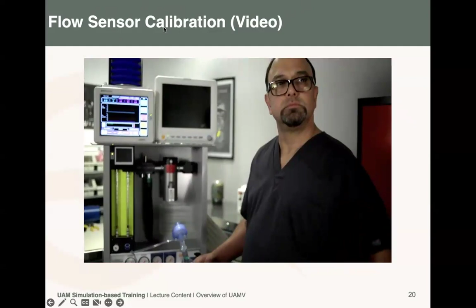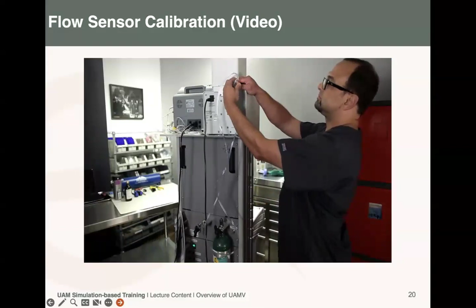Disconnect the ventilator drive hose from the ventilator and attach the red plastic adapter to the 17mm bellows driver taper on the rear of the ventilator bellows assembly. Connect the patient flow sensor with the flow in the patient direction. Blue line closest to the patient, clear line closest to the ventilator. To first calibrate in the forward direction, press the Flow Cal button. Press Calibrate Patient Flow. Press Yes to start calibration of the inspired flow. When prompted, turn the flow sensor around to calibrate the expired flow and press the Continue button. Note: the ventilator will prompt you to put the sensor in the correct orientation if it is connected incorrectly.